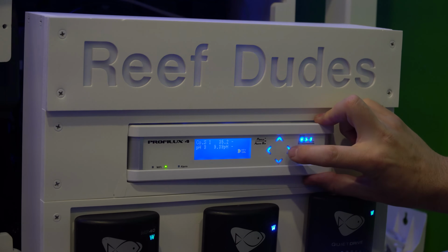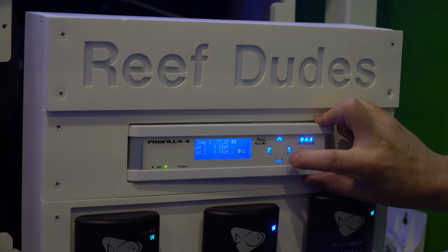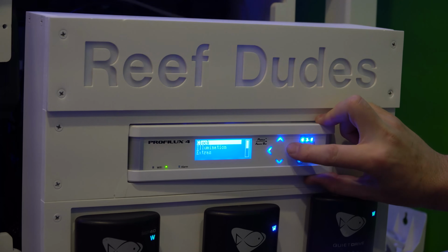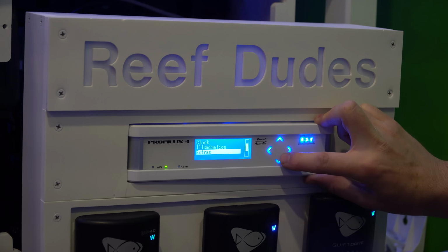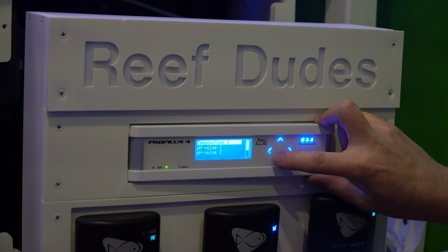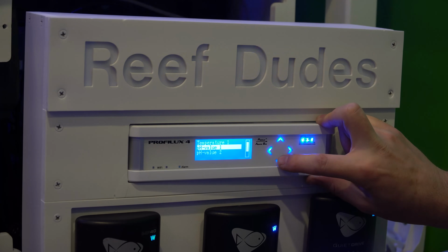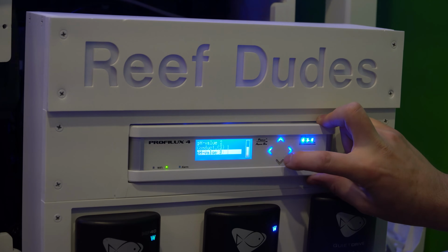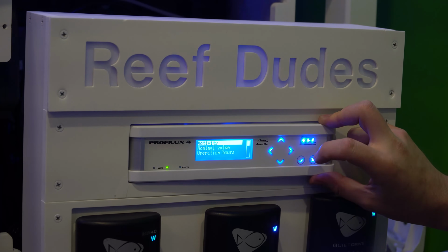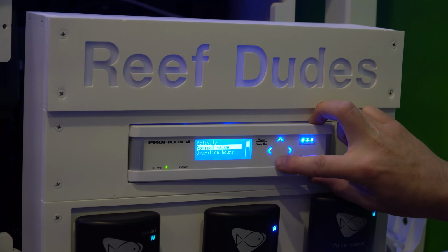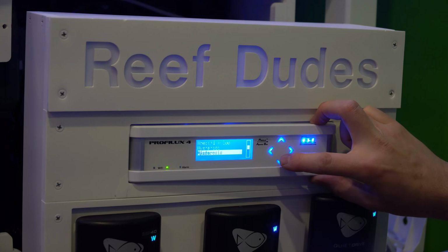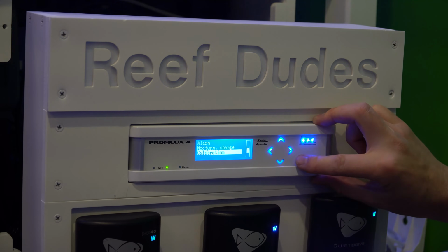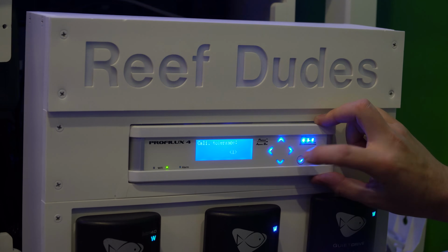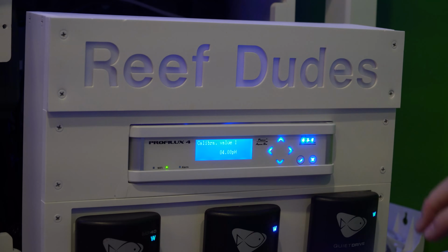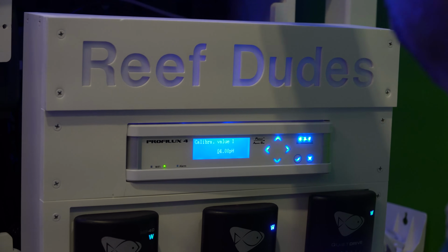So we're gonna hit one of the arrow keys. Sensor settings, and this is an add-on card, so should be pH value 3. Go down to calibration. All right, so first calibration value is 4. So grab our pH 4 packet.